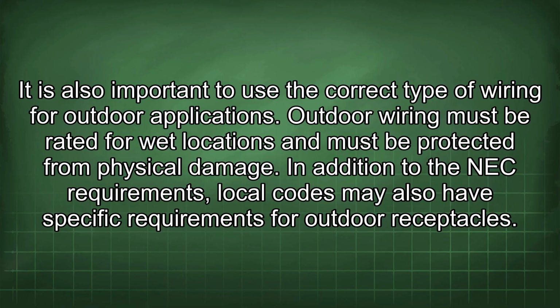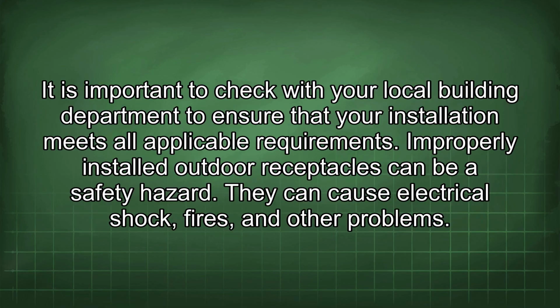Outdoor wiring must be rated for wet locations and must be protected from physical damage. In addition to the NEC requirements, local codes may also have specific requirements for outdoor receptacles. It is important to check with your local building department to ensure that your installation meets all applicable requirements.